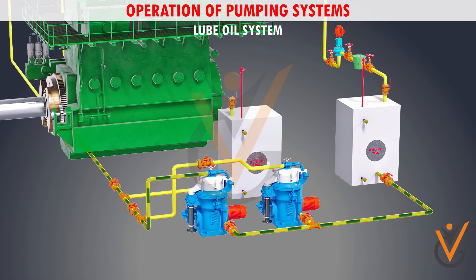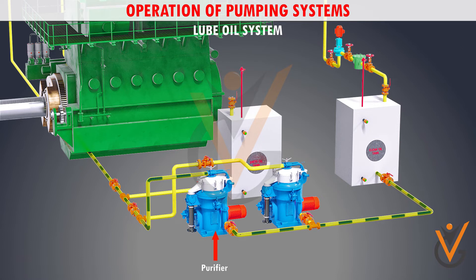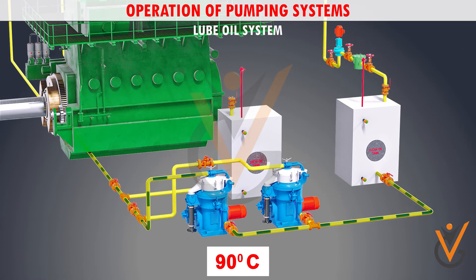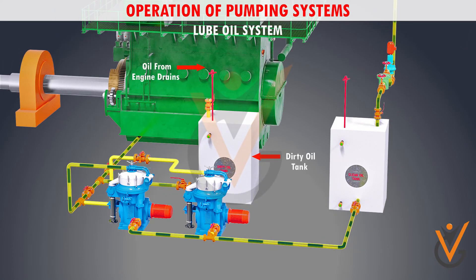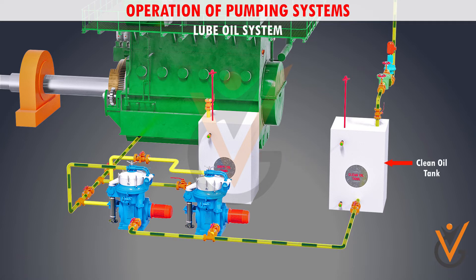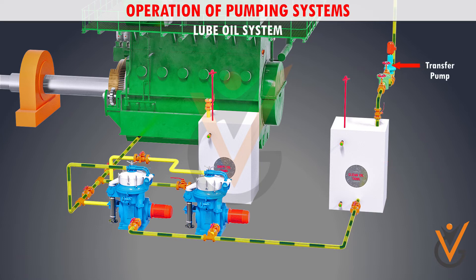The main engine lube oil purifier takes suction from the main engine lube oil sump and purifies the oil. Its temperature is maintained around 90 degrees Celsius to allow efficient separation. The engine drains are connected to the dirty oil tank, from which the lube oil purifiers also take suction, and the purified oil is transferred to the clean oil tank, from where it can be reused by transferring it back to the engine sump using a transfer pump.